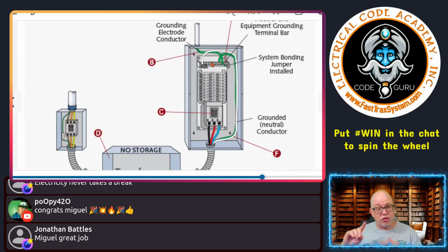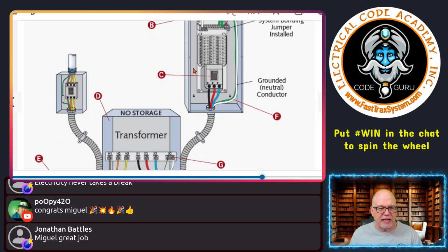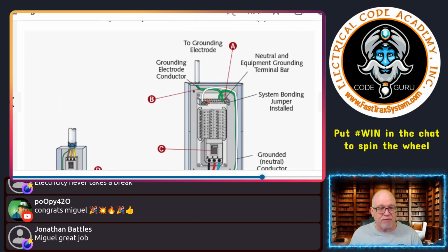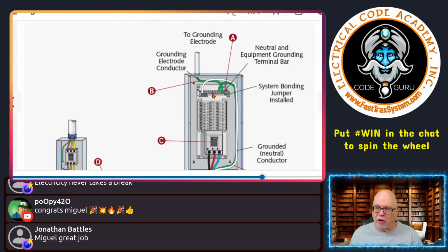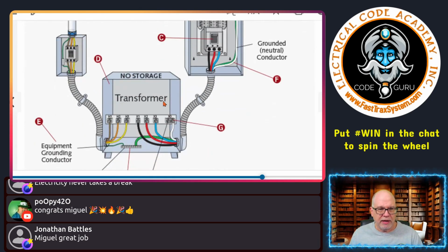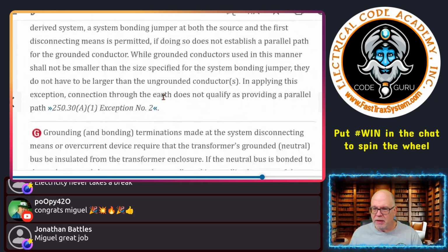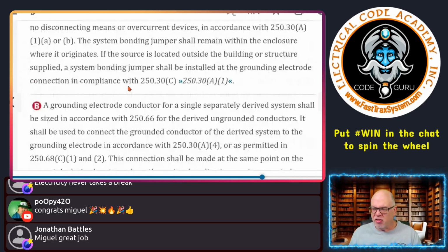And the code allows for you to do it at either or. Just typically not both, unless you can meet the rules, that there are non-conductive paths between them, that type of thing, and you're not creating any objectionable currents, then you could have it at both locations. But again, for the most part, either or, here or here, either one, but not both. All right, so that's where we go there.